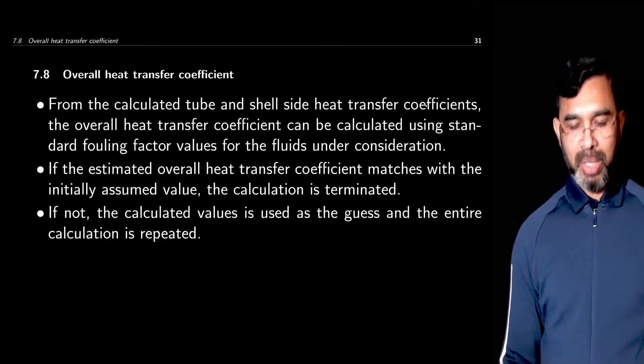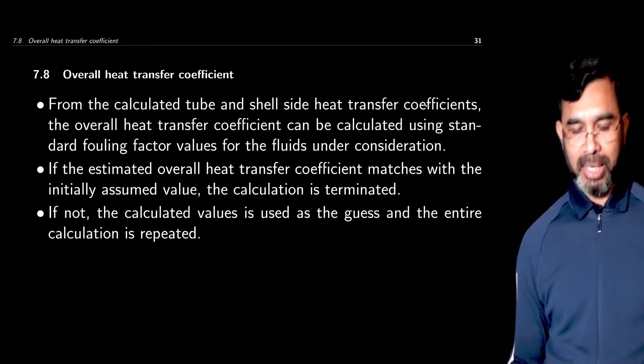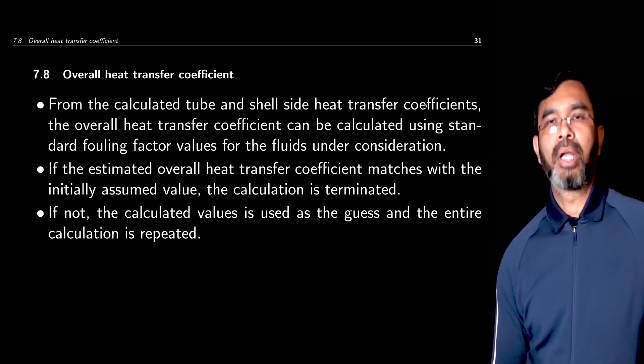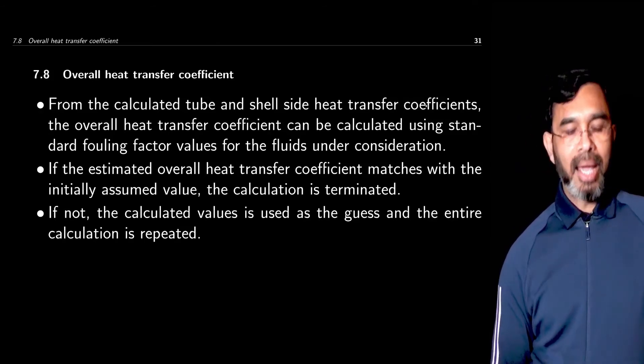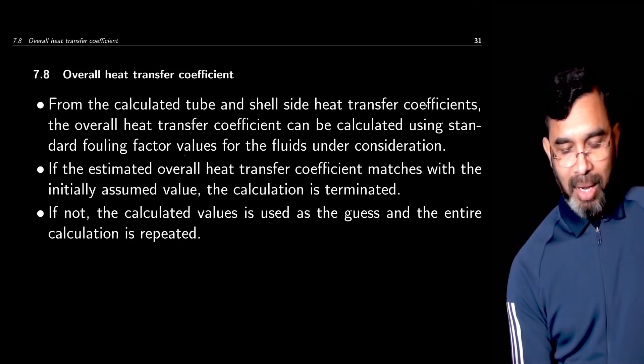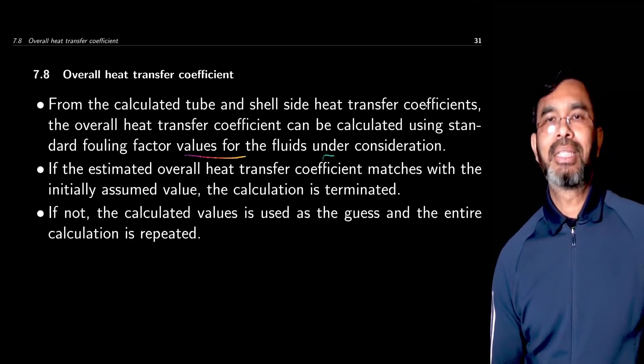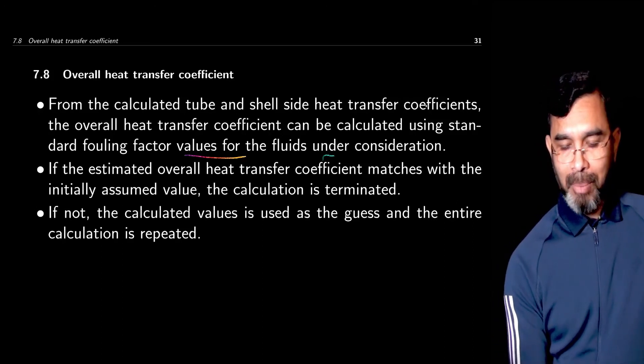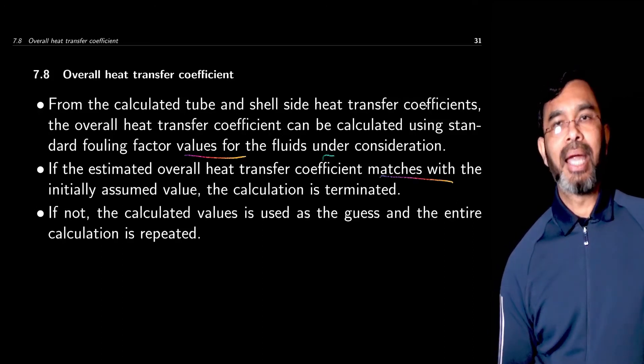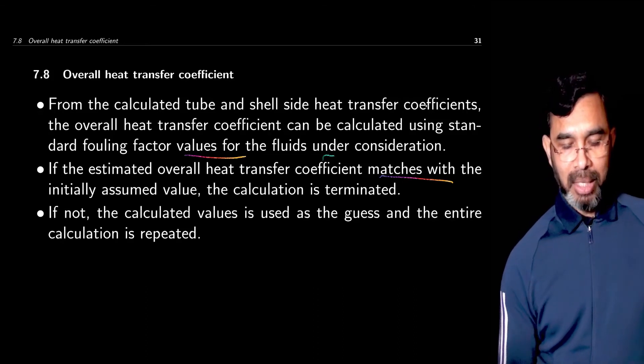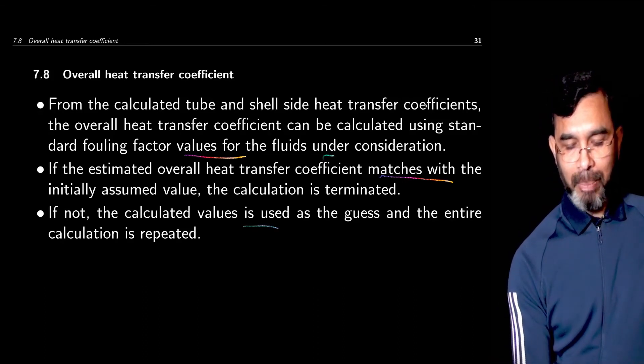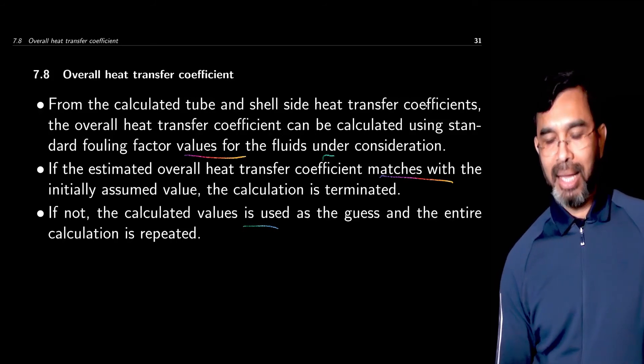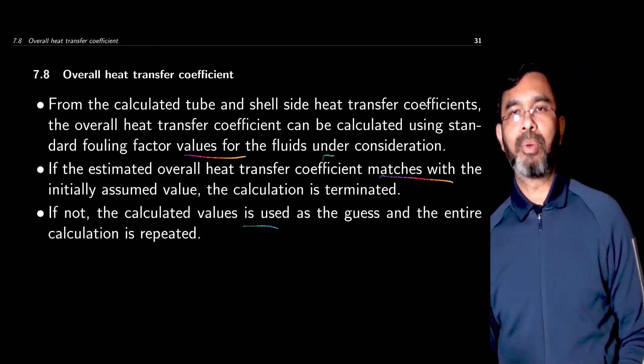Once the shell dimensions and baffle configurations are selected, the shell side heat transfer coefficient can be calculated from the flow and fluid properties. Knowing the flow rate determines the flow area, which gives the flow velocity of the shell side liquid, from which the shell side heat transfer coefficient is estimated. Once you have both the tube side and shell side heat transfer coefficients, along with the material of construction, you get the conduction heat transfer coefficient. Using standard fouling factor values for the fluids, you can calculate the overall heat transfer coefficient. If it matches the initial assumed value, the calculation is terminated; otherwise it is repeated with the new estimated value as the guess.